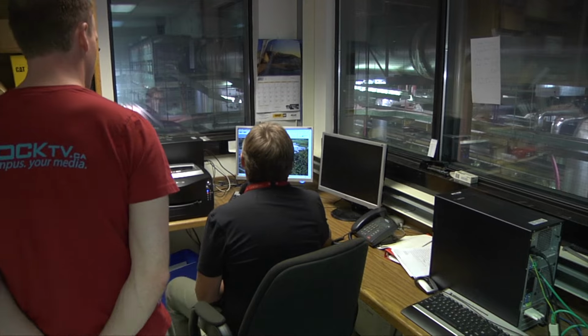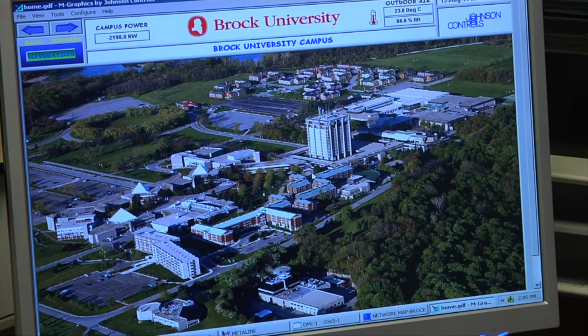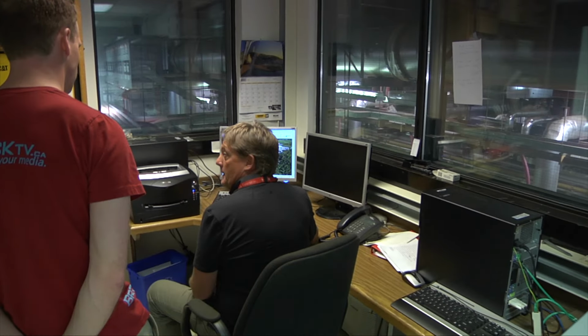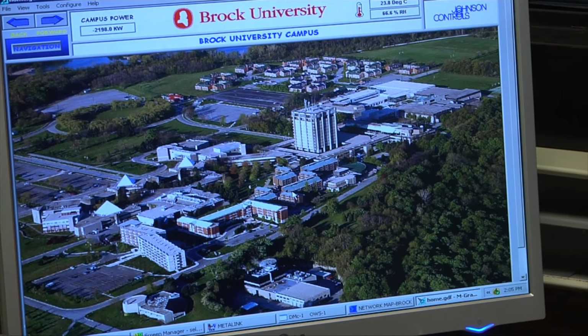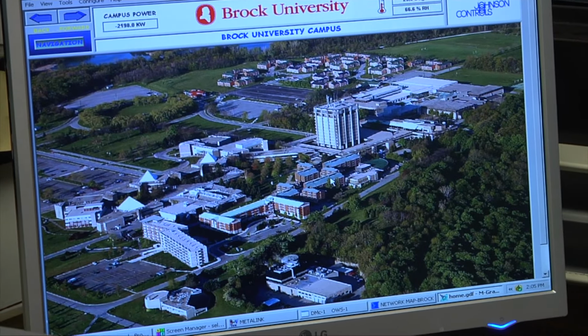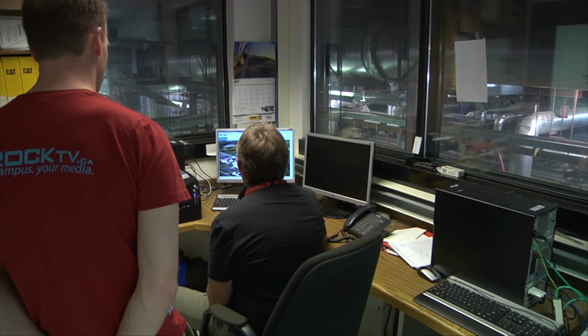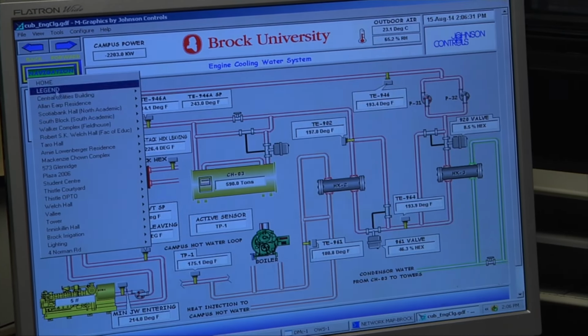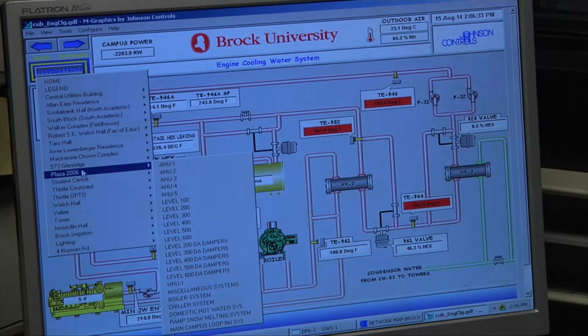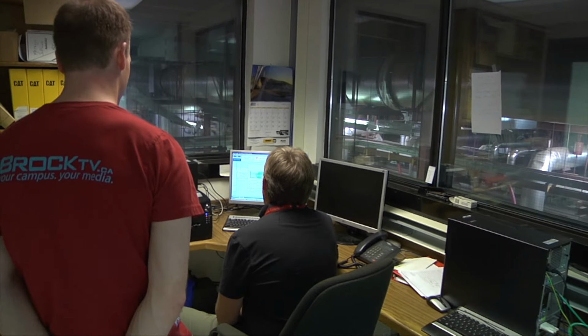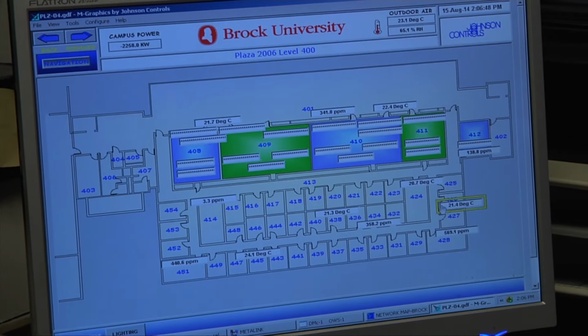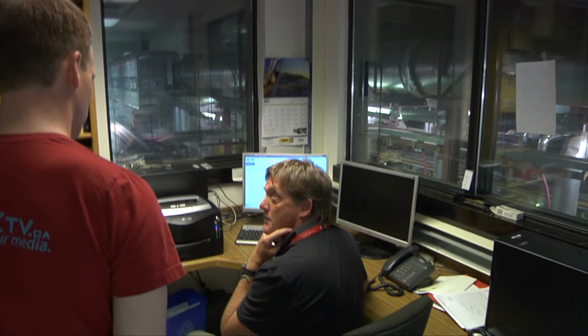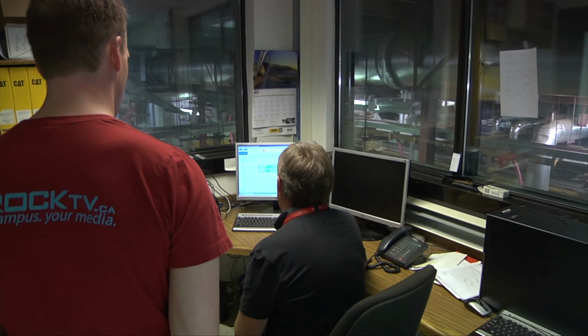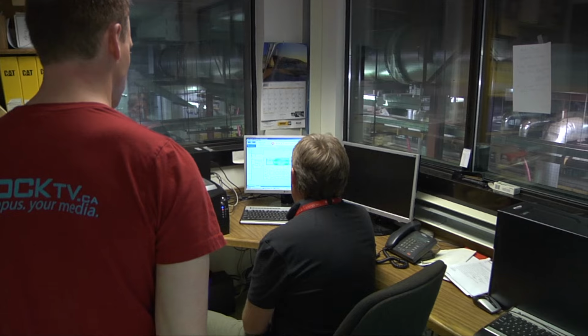What we're looking at here is an overview of the campus on our BAS system, which is Building Automation Systems. We can control 90% of the campus temperatures, fans, and HVAC units from this position. Then I can go to individual buildings, to individual offices. This is Plaza we're looking at right now. Not only does it give me temperatures, 21.4 in these offices, it also gives us carbon dioxide levels in some of the bigger labs, so we can monitor that and bring more fresh air in if they're getting too high.